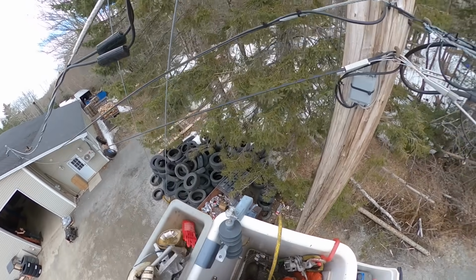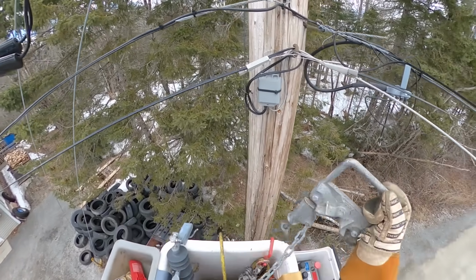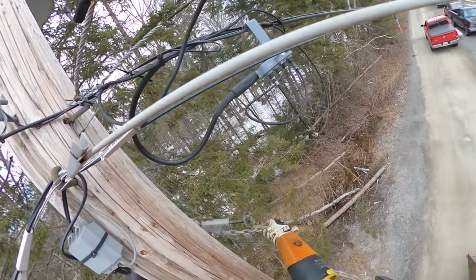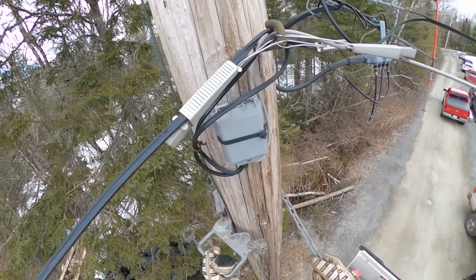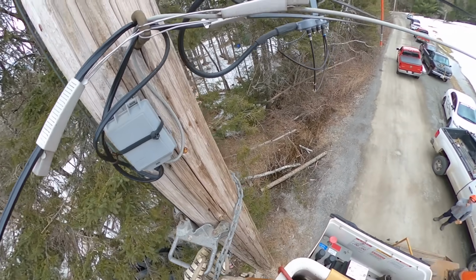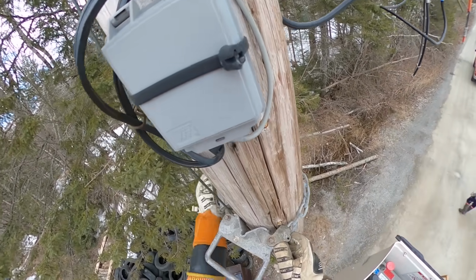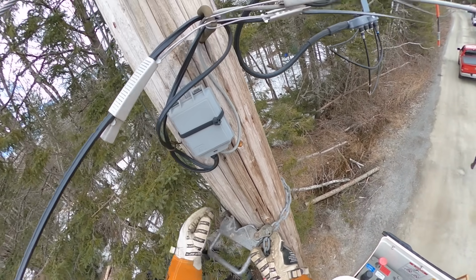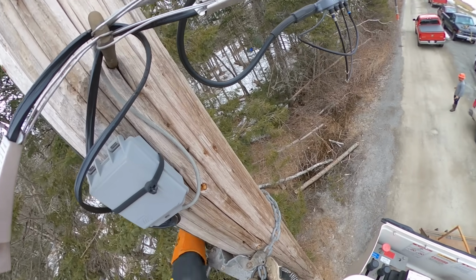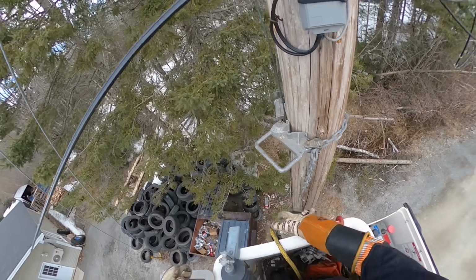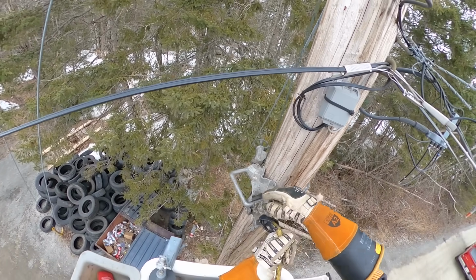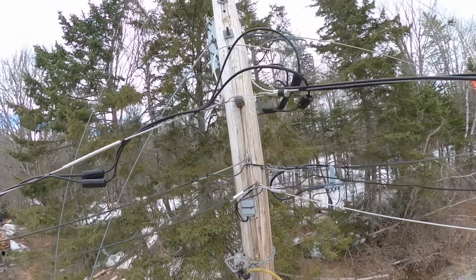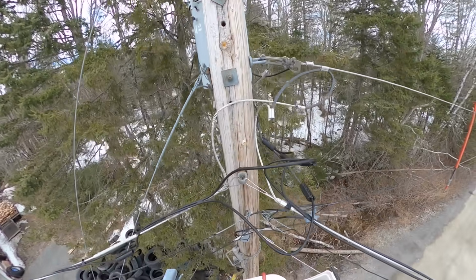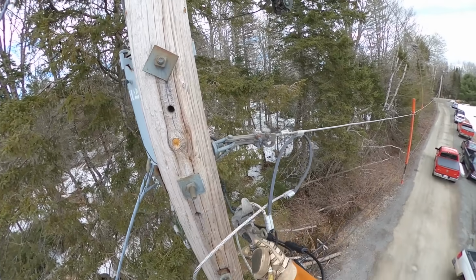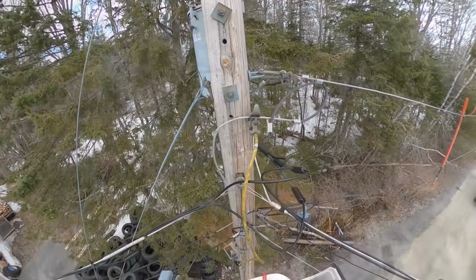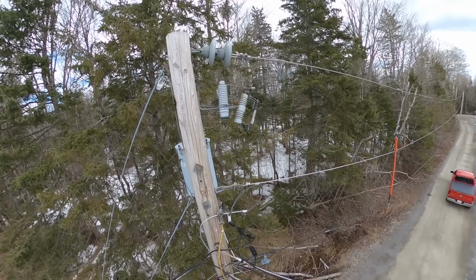So we just hang that in place, and our next step is to go over the pole and install our cluster bar. The purpose of this is a little bit redundant because the neutral is attached to a bolt that's not on an insulator, and that bolt goes right through the pole. So ultimately, if the primary were to get energized, that voltage would travel through the neutral and into the pole. But this is just an extra step within the equal potential bonding and grounding rules, that in the event of, let's say, a lightning strike or backfeed, that voltage will travel around the pole in its entirety through the neutral to make sure that while I'm touching the pole and the conductor, there should be no difference in potential.